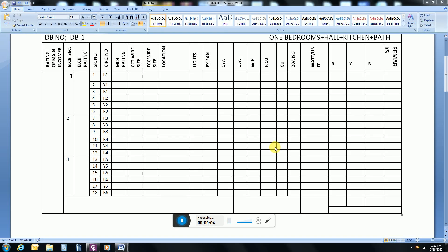Welcome to this new video. Today we are going to make a load schedule for a small flat — a one bedroom hall flat. In making a load schedule, we will make a column for main incomer, then there will be details of the ELCB section. For this small flat there will be three ELCBs: one for lights, one for sockets, and one for AC. I will start from location.